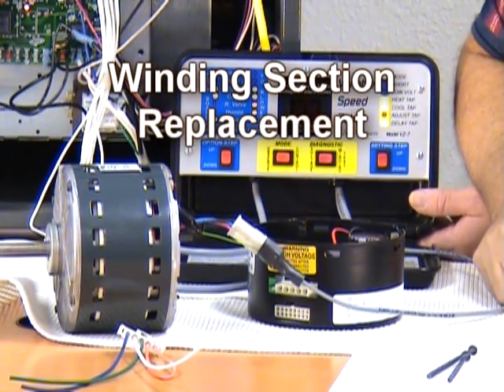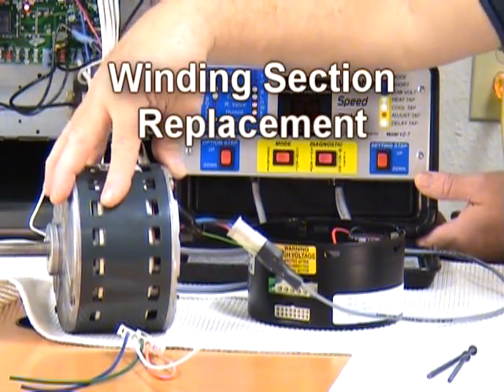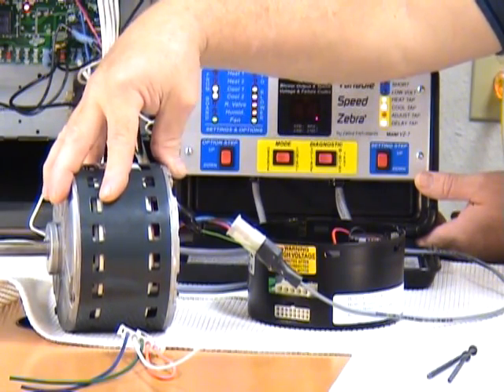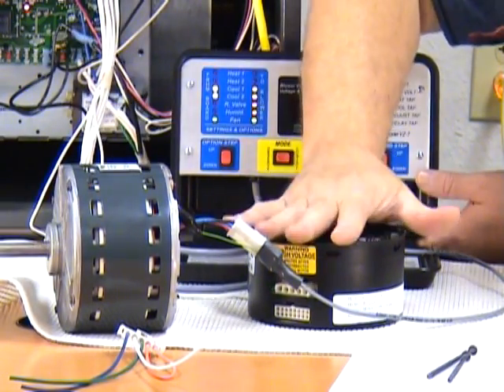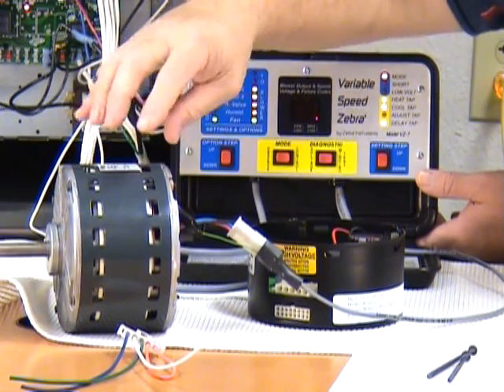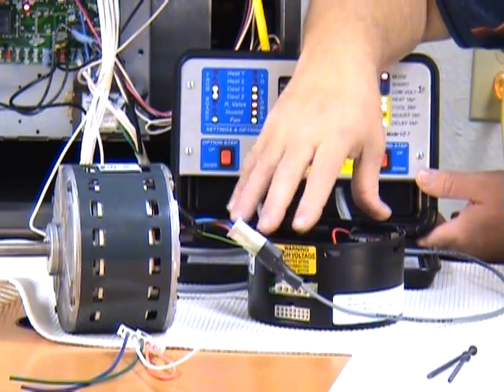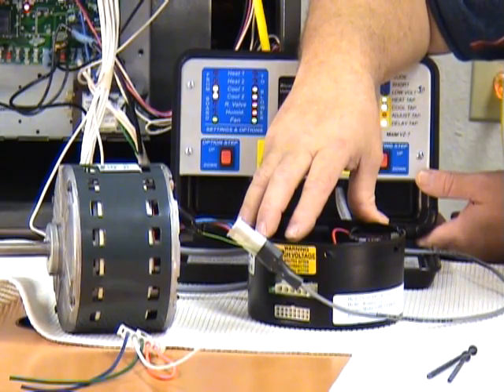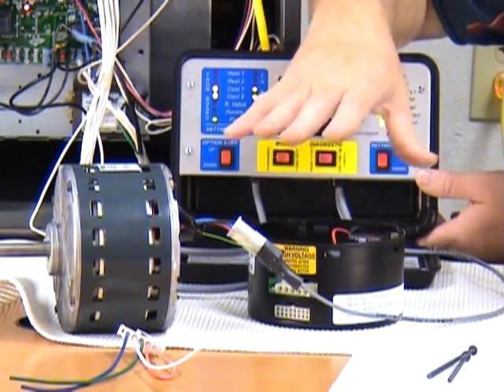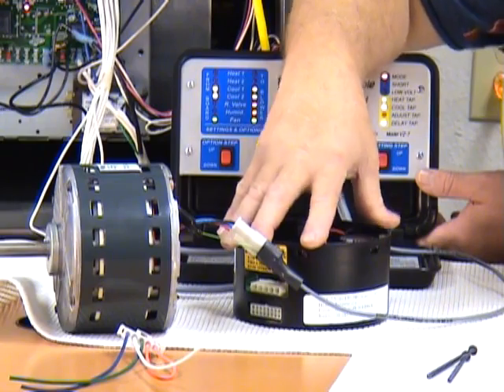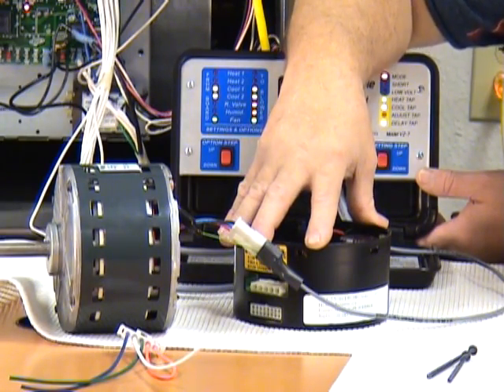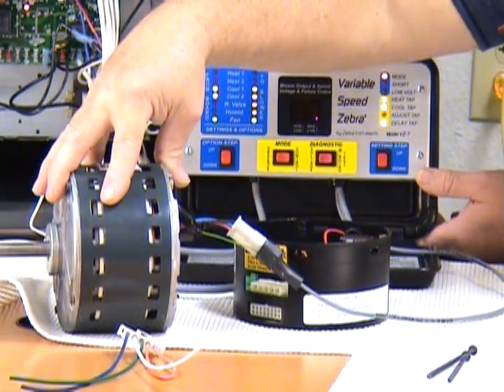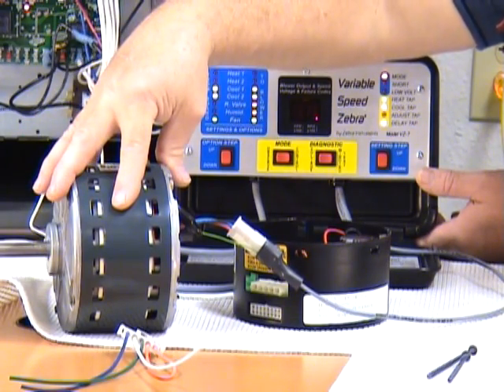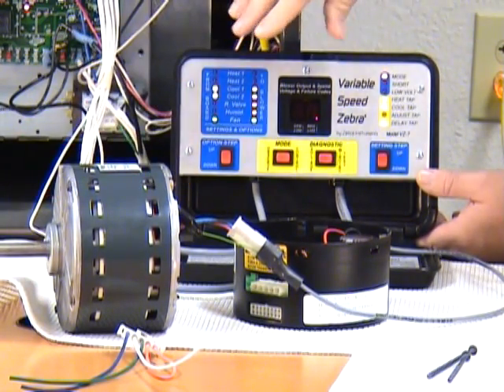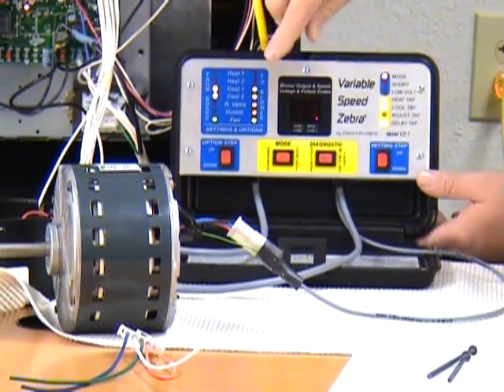One thing you should know about motors in general, if you have a failure in the winding section of this motor, you need to replace both pieces, because any failure in here generally will cause a failure in here. Okay? If you have a failure in the electronics module, unless your manufacturer requires it, you don't have to replace the winding section. It's far more expensive to replace the winding section. So again, let's go through that winding test.